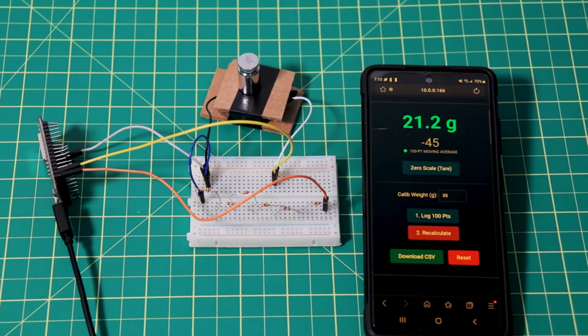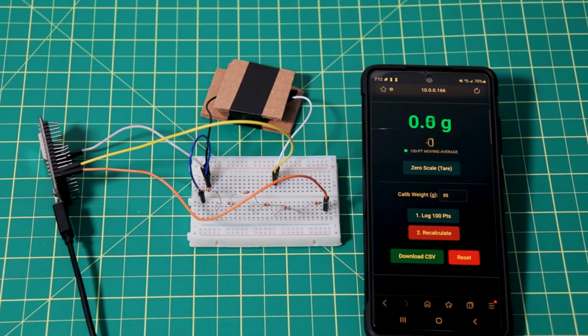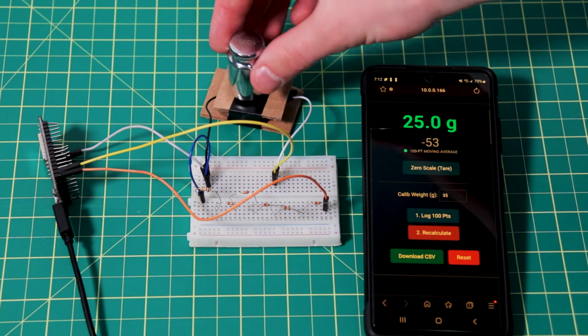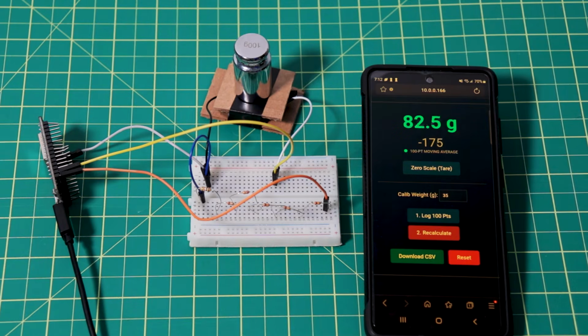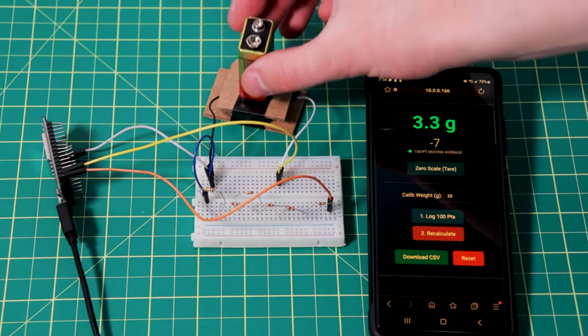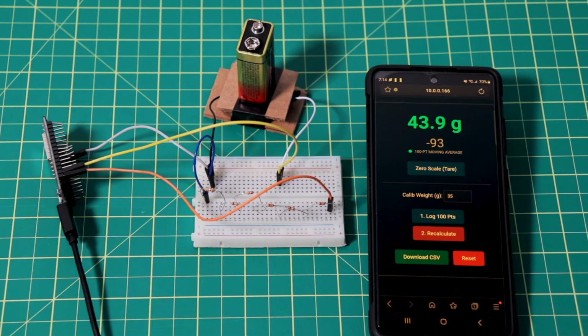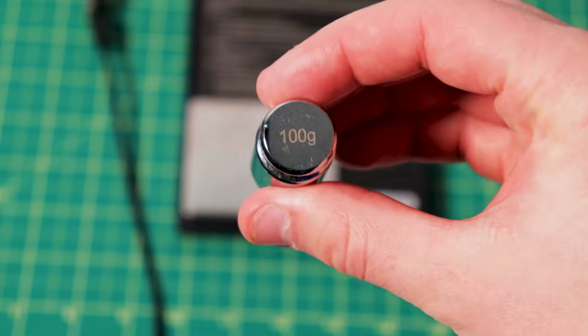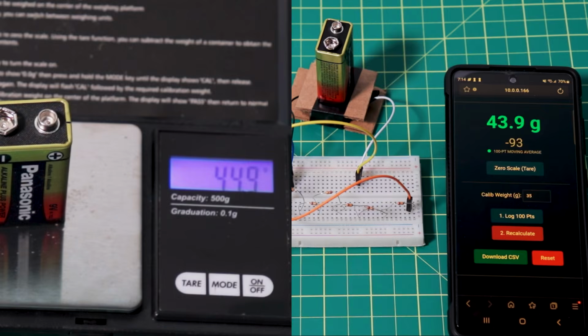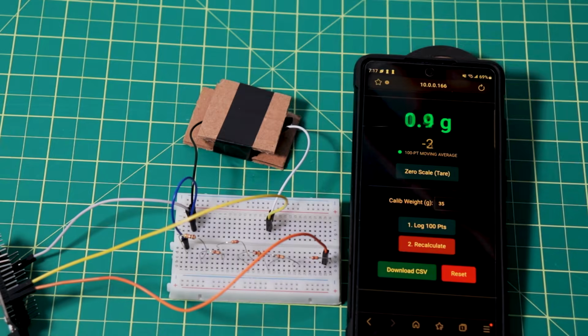After calibrating, I grabbed the known mass of 20 grams and placed it on top of the sensor. After letting the readout settle, it came surprisingly close to the expected value. I then pushed it to the upper limit, 100 grams, and this time it was slightly less accurate, but still within 10%. Honestly, not too bad for a piece of trash. Lastly, I grabbed an object of unknown weight, a 9-volt battery. Our foam scale predicted roughly 42 grams. To fact check this reading, I pulled out a more accurate scale. Our calibrated scale read 45 grams, which, compared to the 42 predicted from the foam scale, is not too shabby.